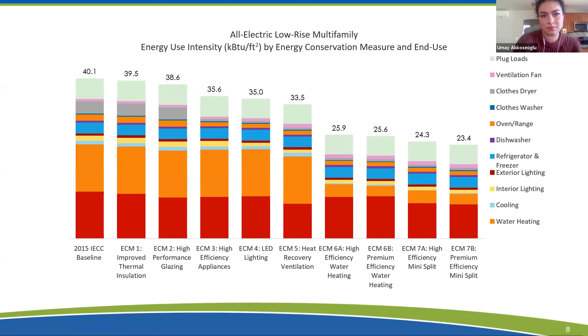This slide is more of a recommendation slide because, although the ZNE program cannot incentivize renewables at this time, we wanted to see what the benefit would be in the model if we generated electricity on site. So what we did is we modeled a 29 kilowatt solar rooftop array that offset approximately 70% of the building's annual energy consumption. From this chart, you can see that if the energy benefit of the solar is considered, the resulting net energy consumption of the proposed case is an EUI of 6.8.